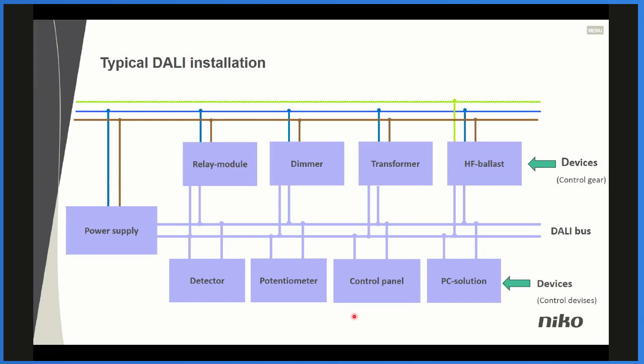DALI's installation, so to speak. This is the main. We have a power supply, and for that power supply we have the DALI bus. This is only 2 wires, and this DALI bus is acting as a supplier to all our devices that we have in a DALI installation, but it's also for the communication. So this DALI bus has 2 ways. It has communication and has to supply all our devices that we have in our installation.